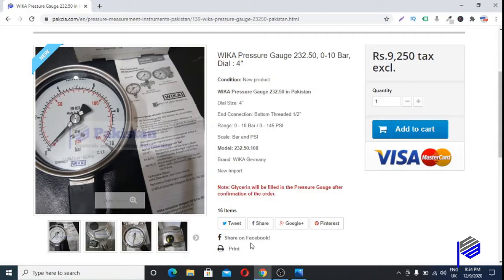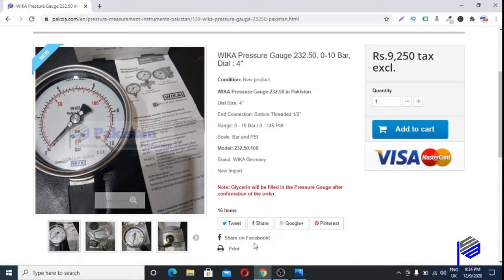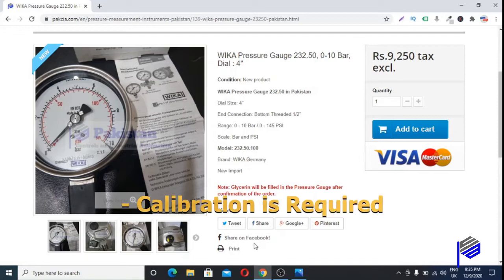We don't import both models — we only import one model, which is without glycerine fill, that is 232.50. If any client requires a glycerine-filled pressure gauge, we locally fill the glycerine inside the pressure gauge here in Pakistan and then calibrate it. Keep in mind: whenever any pressure gauge is filled with glycerine, it requires calibration.